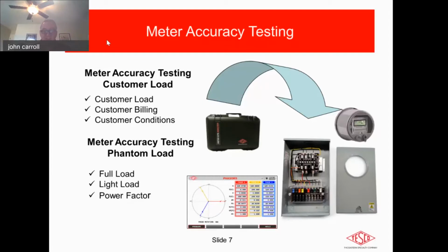On the right-hand side, you'll see a typical installation where you have the meter itself on top, where the meter socket is. Then you have your test switch, which allows us to shunt out the CTs and bypass so we can actually energize and look at the signals coming in. The 2 methods that are the most common are under a customer load or what is known as a phantom load. And there's an important distinction between them.